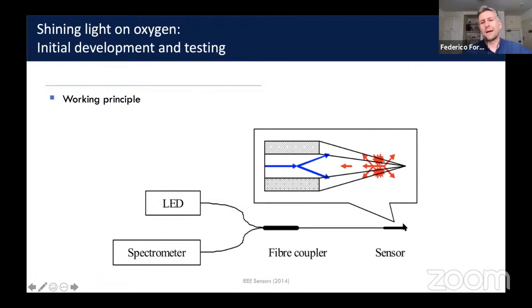then the sensing part of the fiber is illustrated here at the top, where we have blue arrows that indicate the light coming from the LED source, and that bounces around into the tip of the sensor. The red arrows indicate the interaction with the oxygen molecules, and then the red arrows that return into the core of the fiber illustrate the signal, which comes back to the fiber coupler and enters the spectrophotometer.